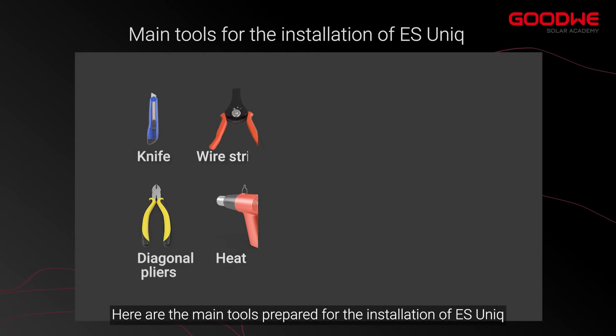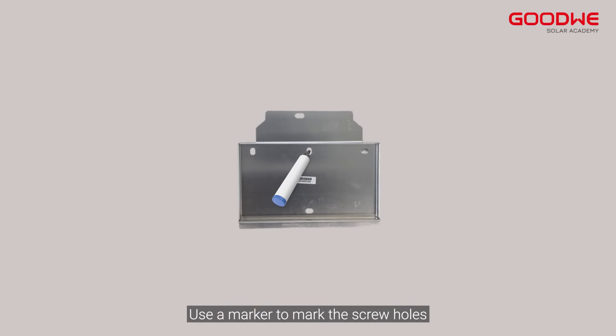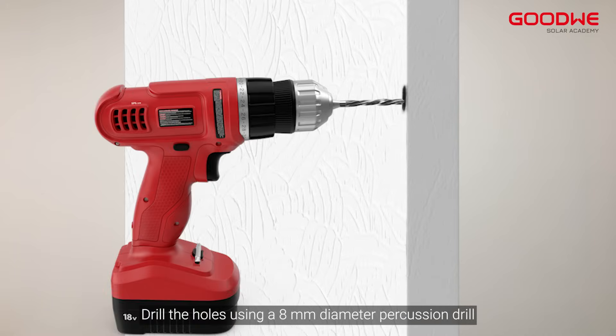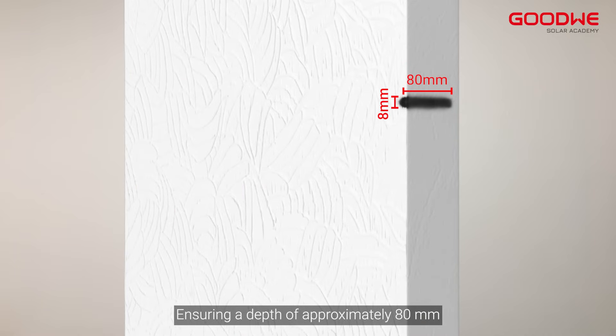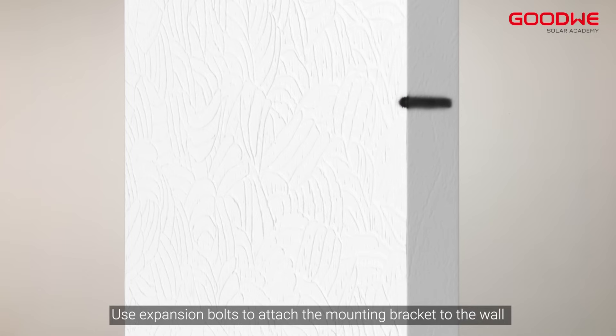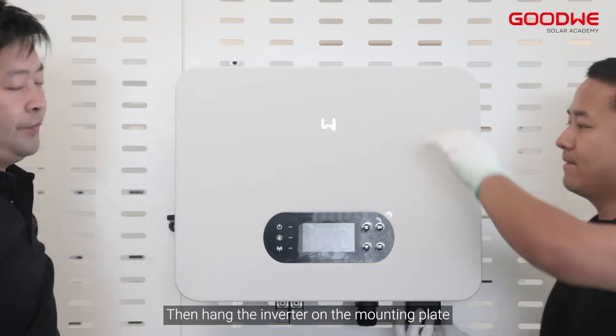Here are the main tools prepared for the installation of ES Uniq. Use a marker to mark the screw holes, then drill the holes using an 8 millimeter diameter percussion drill, ensuring a depth of approximately 80 millimeters. Use expansion bolts to attach the mounting bracket to the wall and fix all four screws, then hang the inverter on the mounting plate.